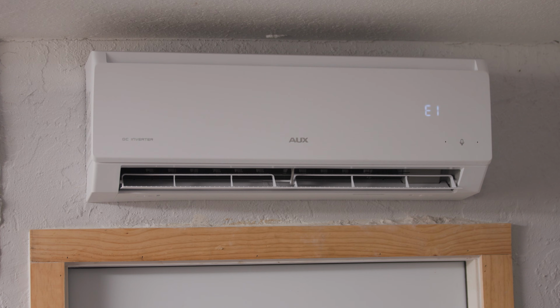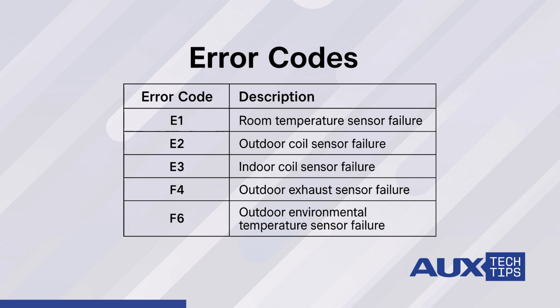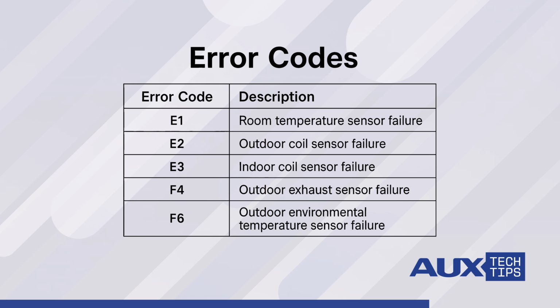Identify the thermistor using the error code on the AUX indoor unit's display. Here are the error codes and the thermistors. Note, multi-zone AUX systems may have additional sensors and error codes. Check your service manual for that model's specifics.